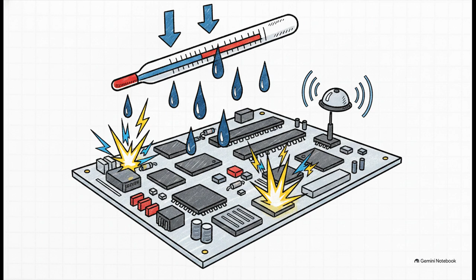But the one we really need to focus on is condensation risk. Let's zoom in on that one right now. A condensation risk status pops up specifically when the facility's water temperature drops below the ambient dew point temperature. And why does this matter? Well, water and high-voltage server electronics do not mix. If condensation forms inside a server rack, it poses a literal life-or-death, catastrophic threat to the hardware. That's exactly why having a dedicated dew point sensor feeding real-time data back to your SCC dashboard is so vital.